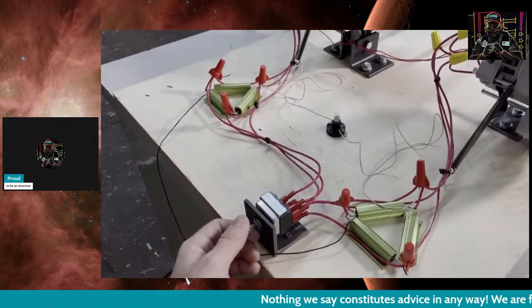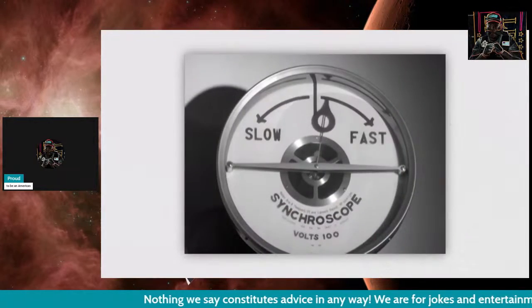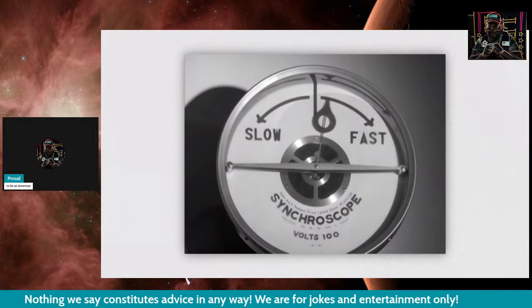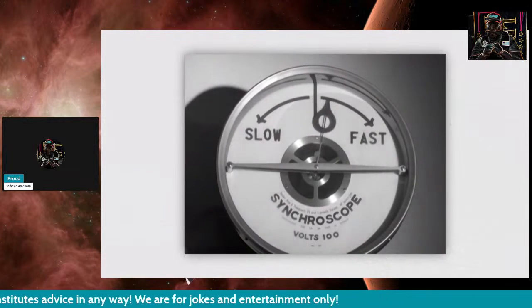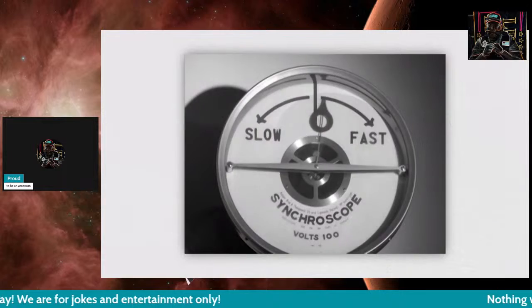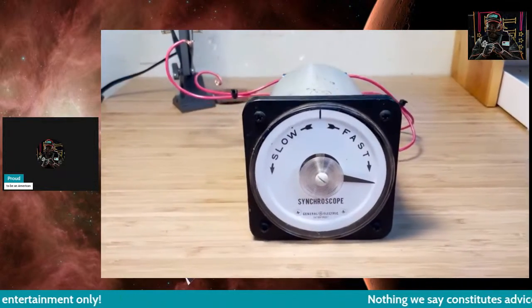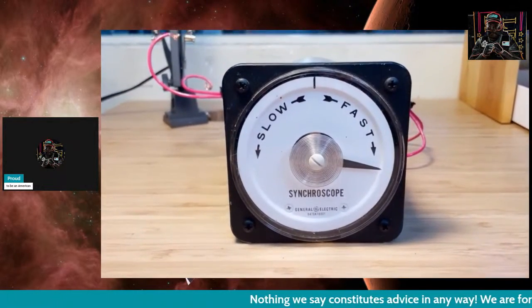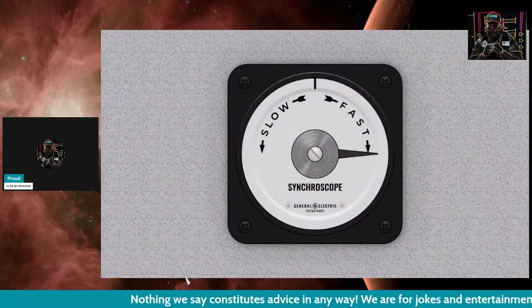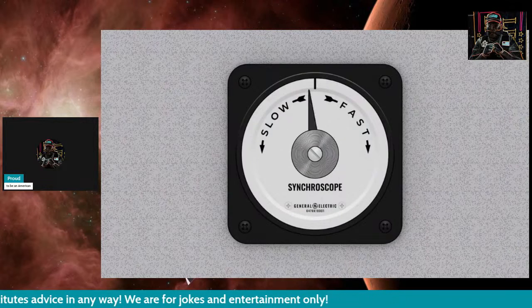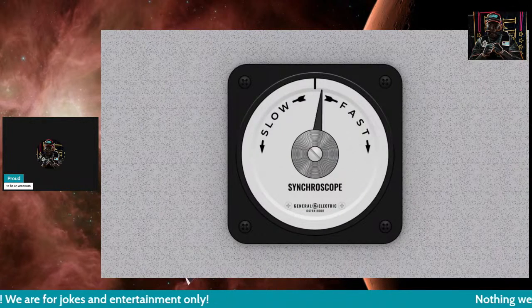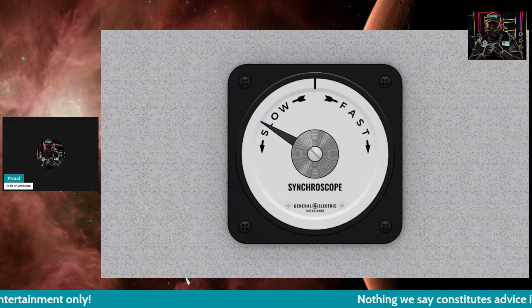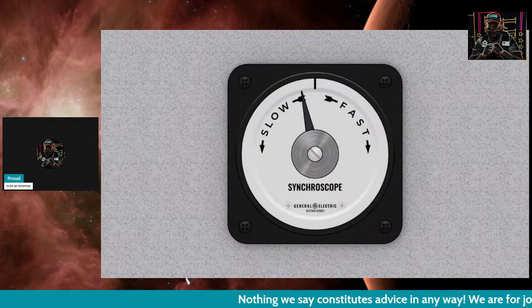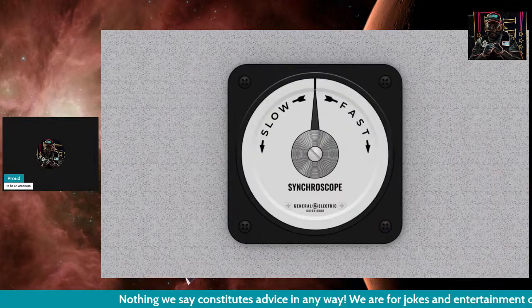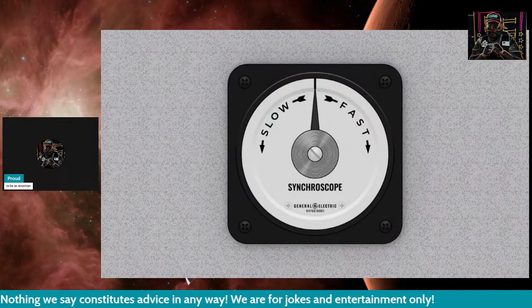There's no voltage difference, meaning you're good to throw the breaker. Older plants were equipped with a synchroscope that would show both whether the plant was spinning at the same speed as the grid, or faster or slower, and whether the phase angle was a match. I bought an old one for this video, but it needs much higher voltages than I'm willing to play with in the studio, so let's just animate over the top of it. Operators would manually bring their generators up to speed, making slight adjustments to match the frequency of the rest of the grid. But matching the speed isn't enough, you also have to match the phase. So this was a careful dance. As soon as the synchroscope needle both stopped moving and was pointing directly up, the operator could close the breaker.